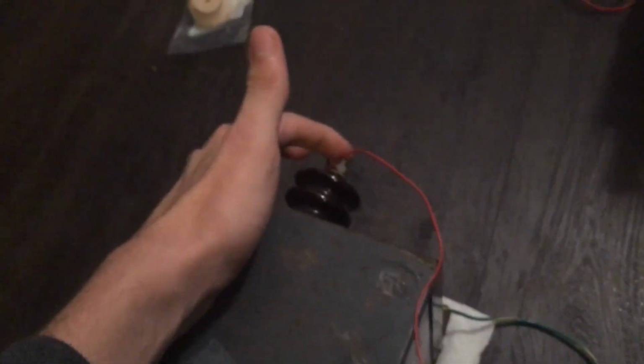There's a good way to test this too. I strap a wire to one of the lugs on the transformer, and now on this line there's 7,500 volts. You don't want to touch this—I use a cardboard rod. You can use PVC. Wood's not a great idea, but you get the point.